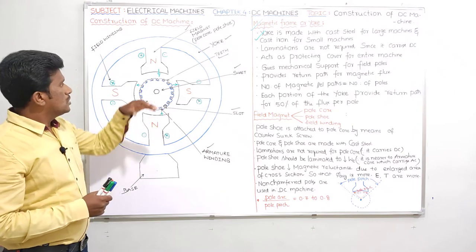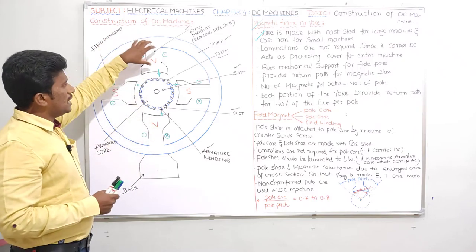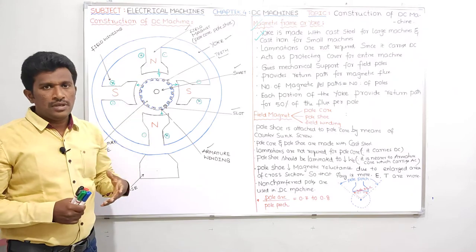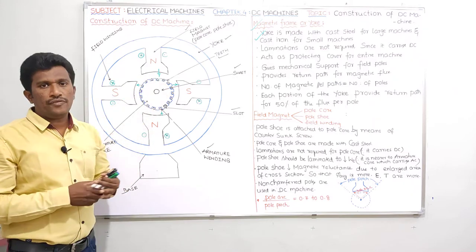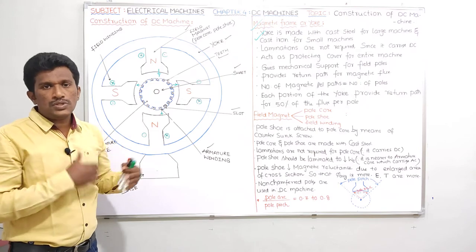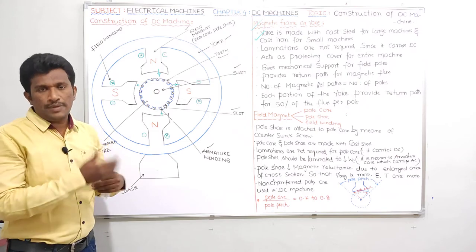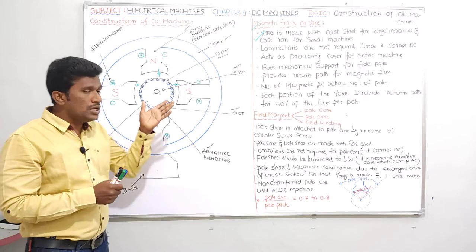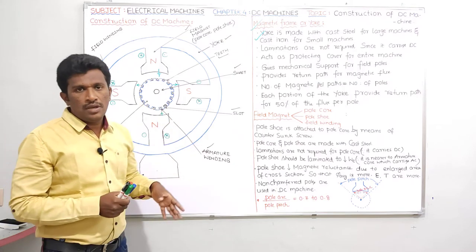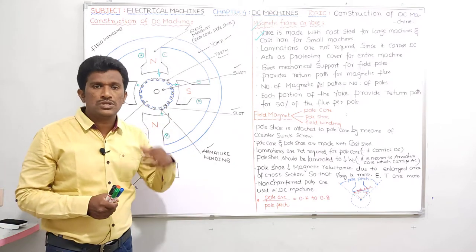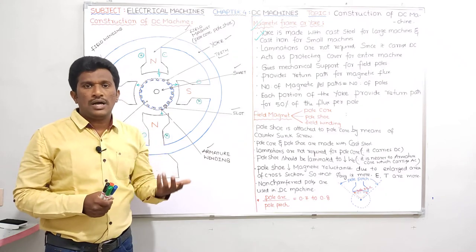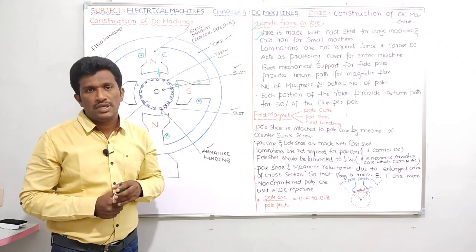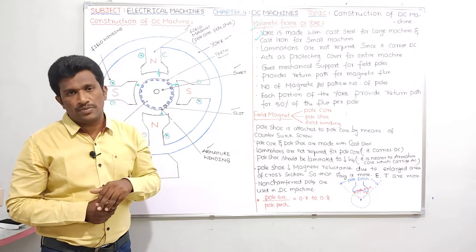Now here, between the stator and rotor there is an air gap. Because of the air gap, which offers high reluctance, there is no improvement in the permeability. So there is no need to use CRGO silicon steel here. If I use CRGO silicon steel, whose flux density value is more, you will have more hysteresis losses, which is not desirable.